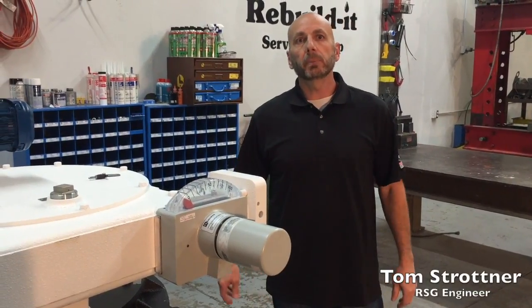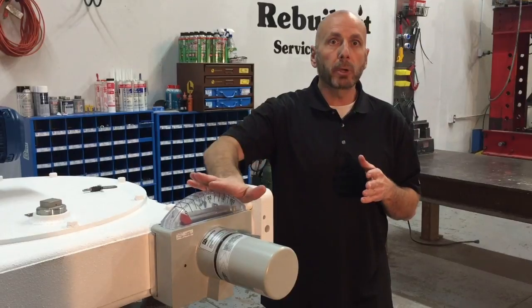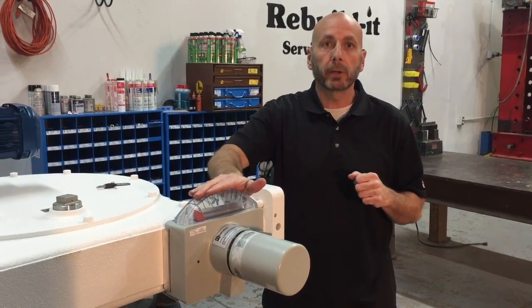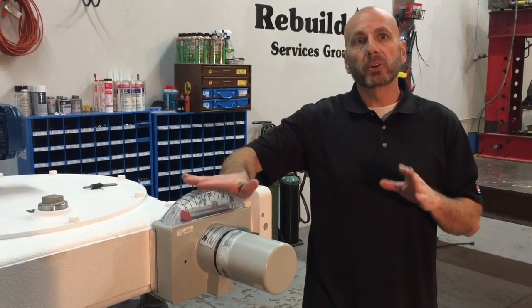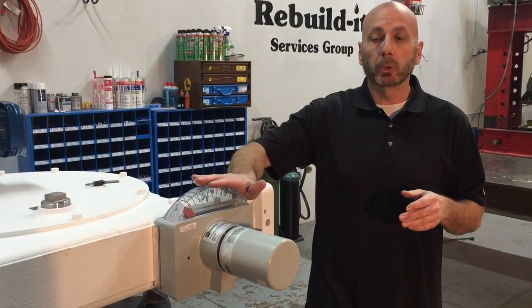Hi, this is Tom with Rebuild-it Services Group. Today I want to do a quick instructional video on how to test your Eimco drive control, which is located on your Eimco drive head on your clarifier or thickener mechanism. The drive control is kind of the heart or the brain of your clarifier. It is there to prevent you from having costly damages due to a torque overload device.